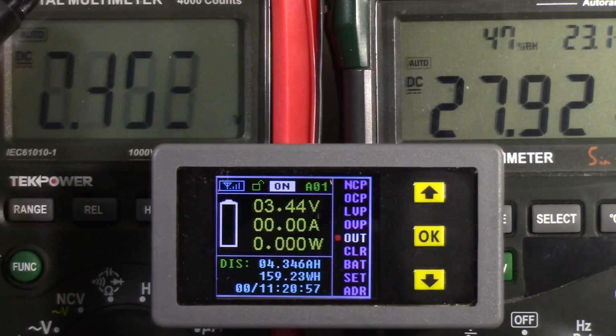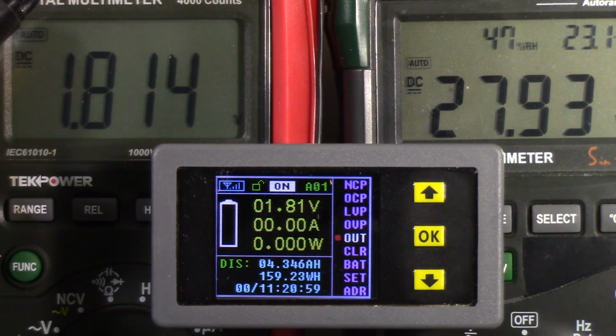So there you saw how it just turns off, goes down to 1.81 volts, and it's just done. Basically, it's shut down. I'll slow that down to show you exactly what the cutoff point was, but it's around 27.8 something, which is higher than the cutoff by the manufacturer of 2.75 volts for each cell. So at 27.8, we're still safe on that, on every cell in that battery pack, which is really nice. So that's it on the low cutoff point.